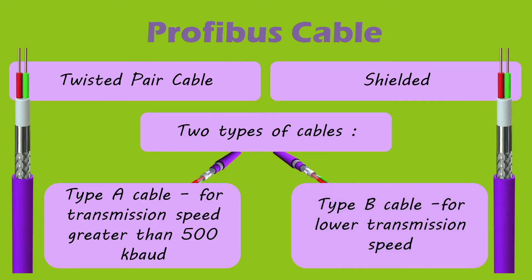Profibus uses a twisted pair cable with shielding, though shielding is sometimes not provided in application-specific cases. Usually, Profibus cables in use are shielded. There are two categories of cables: Type A, used when the transmission speed is greater than 500 kbps, and Type B, used for short distances and low baud rates.